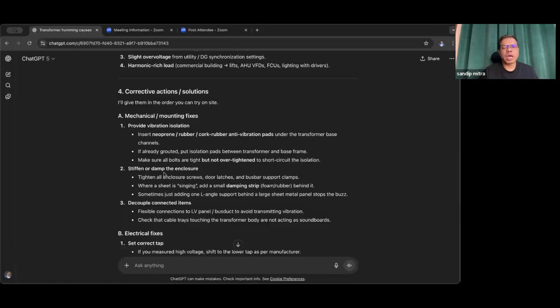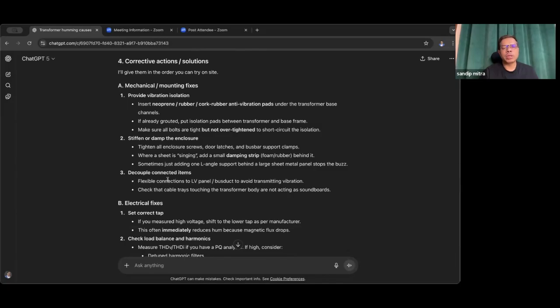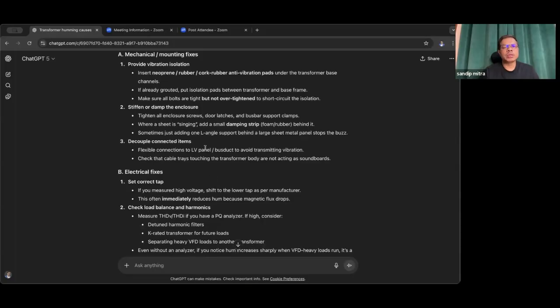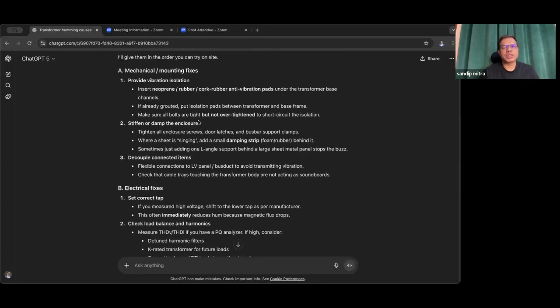Then stiffen or damp the enclosure. Tighten all the enclosure screws, doors, latches, and busbar support clamps. Where a sheet is vibrating, add a small damping strip. Sometimes just adding one L angle support helps. Then decouple connected items. Use flexible connections to the LV panel or bus duct to avoid transmitting vibration. Check the cable is not touching the transformer body. These are the mechanical fixes.